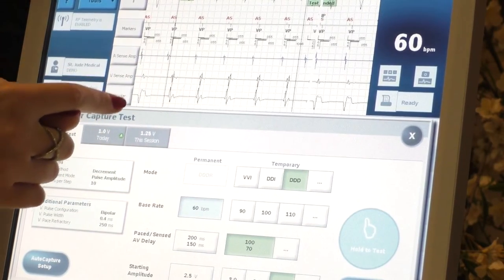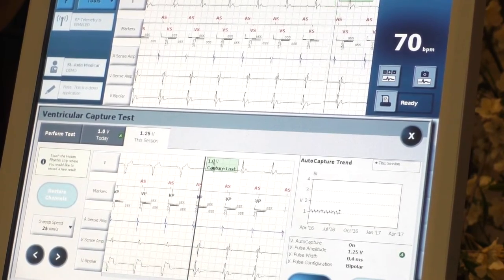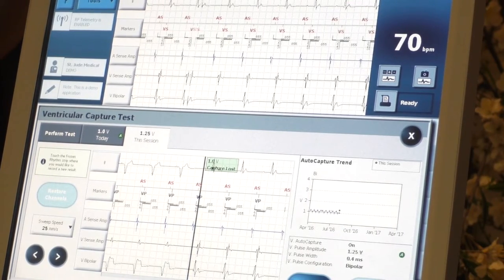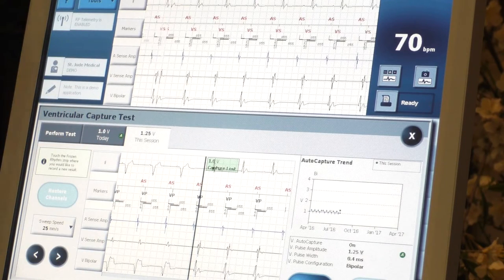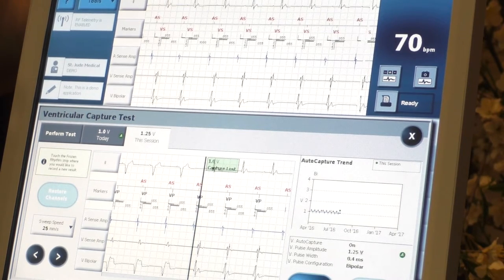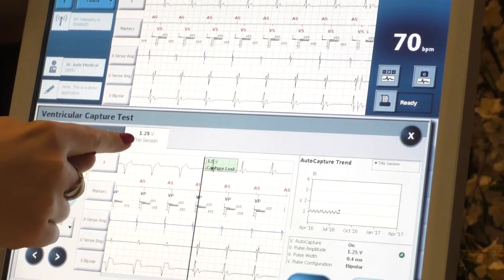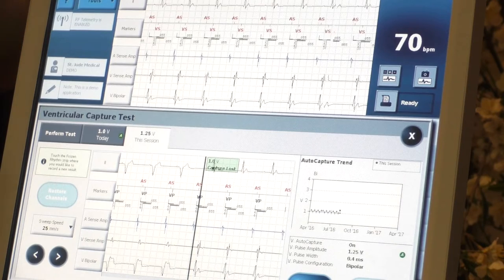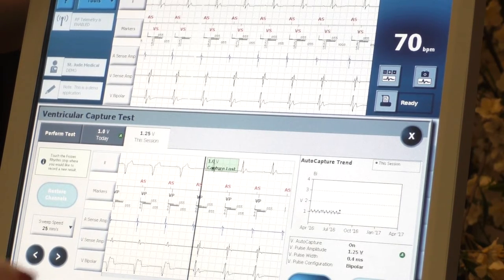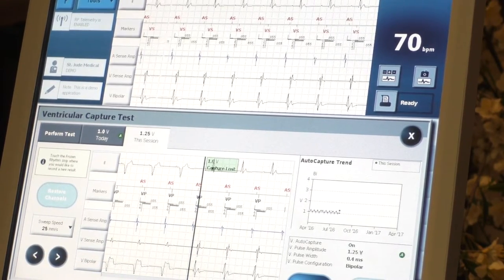So we lost capture at one volt. You touch where you lost — that's the point where you don't want it to happen in real life. We do these threshold tests so we know how to program the outputs in real life. It's the minimum amount of voltage that has to be given in order to pace the heart. So the threshold is 1.25 volts at 0.4 milliseconds — a voltage applied for a certain time. The threshold is the last beat captured before you lost it.